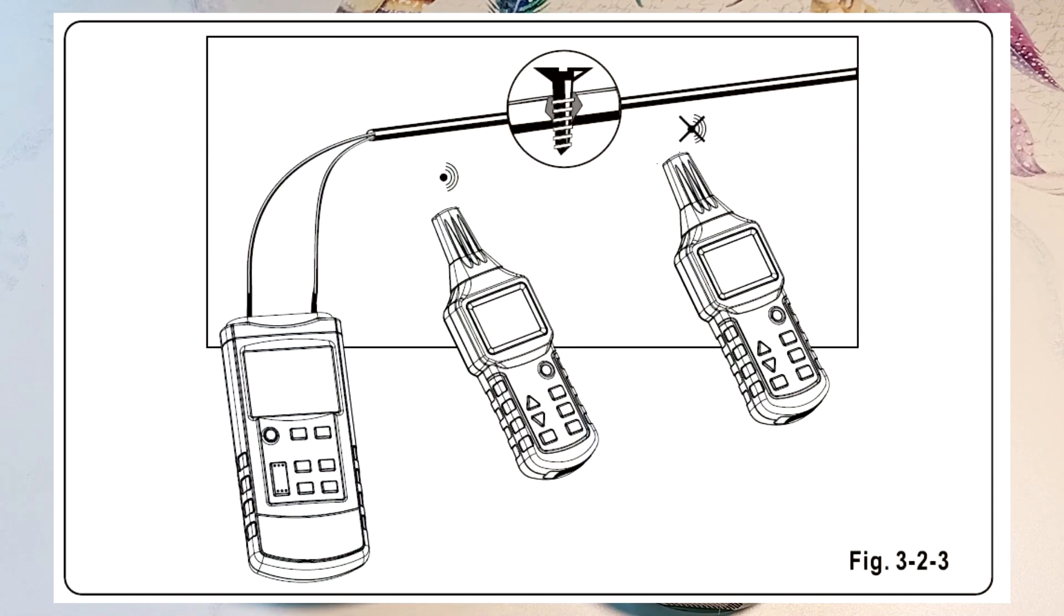This shows short circuit detection. The circuit must be de-energized. Connect the generator to the wires that are shorted. Short circuits with a resistance of less than 20 ohms are correctly detected. To more accurately identify the location of the short circuit, the wire after the location of the short circuit should be grounded.